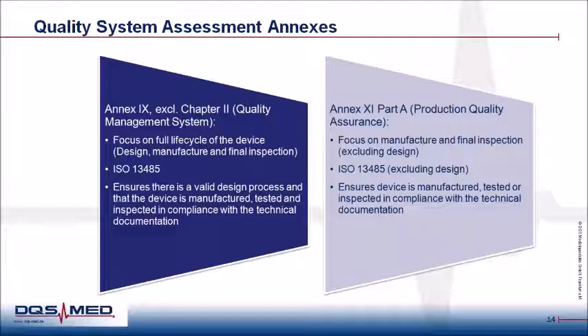So in the MDR, the annexes can be grouped as quality system assessment annexes and product assessment annexes. The quality system assessment annexes are Annex 9, excluding Chapter 2, and Annex 11, Part A. Annex 9 is used when a full quality management system is implemented by the manufacturer. It is based on ISO 13485, considers the full life cycle of a medical device, including design and manufacturing aspects, and confirms that the design process, manufacturing, and corresponding inspections are aligned with the technical documentation. Depending on the device classification, full or partial compliance to Annex 9 may be required.